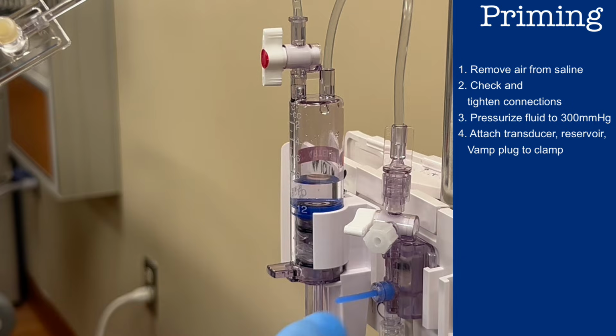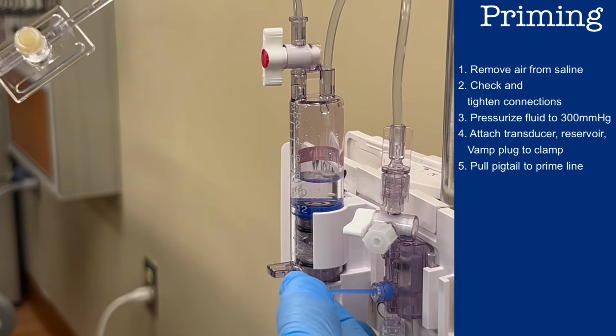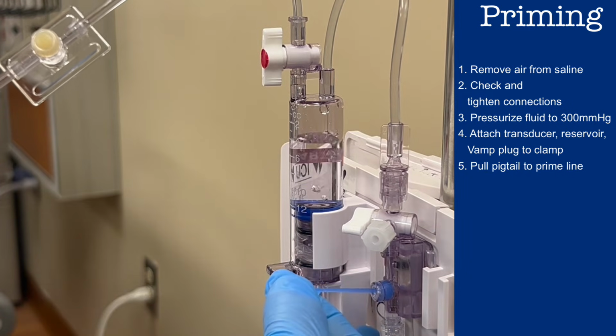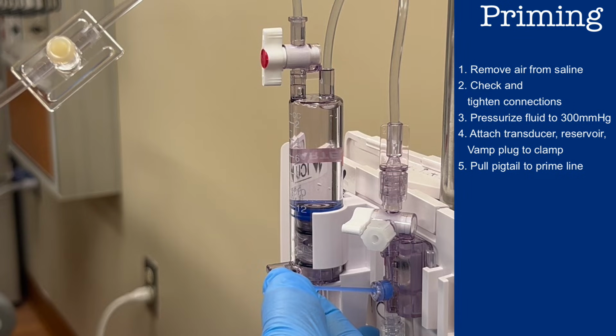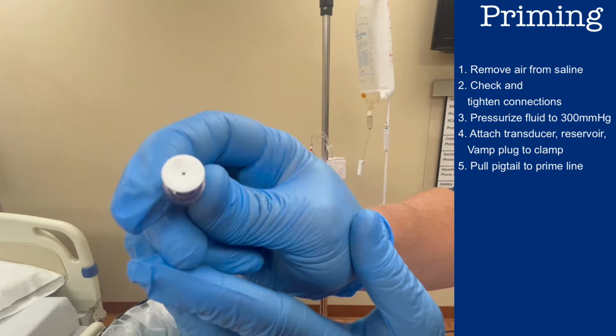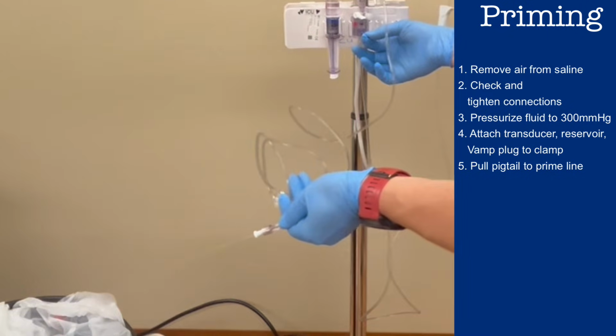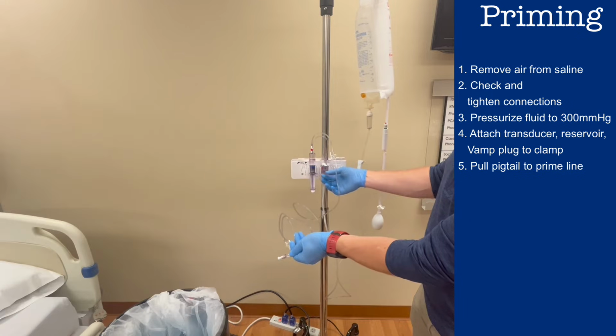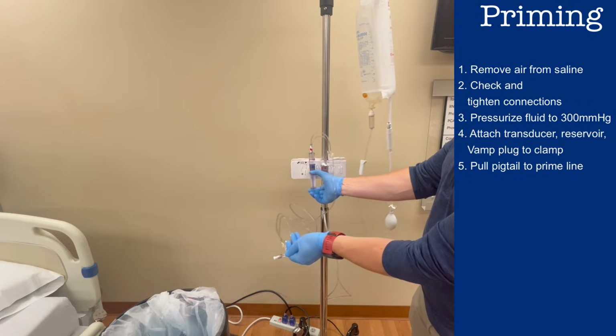You'll need to clear all air from the system. Do this by pulling on the small blue pigtail on the transducer. You will see fluid begin to immediately fill the tubing until it reaches the reservoir. That will fill, and then continue to prime the rest of the tubing. The patient end of the tubing is packaged with a small white cap over it. The cap has a small hole, so when fluid reaches the end of the tubing, it will shoot out in a fine stream. Drain it into the sink or the trash. Return to the reservoir.